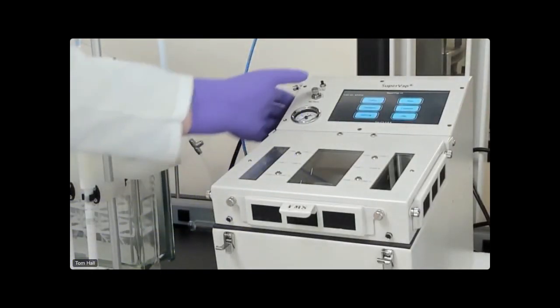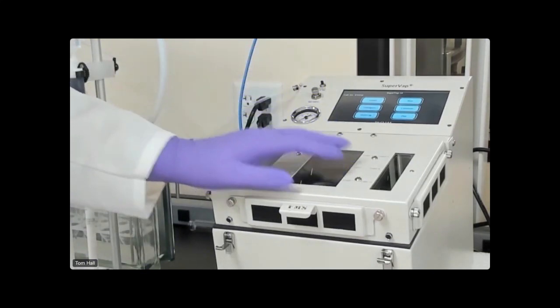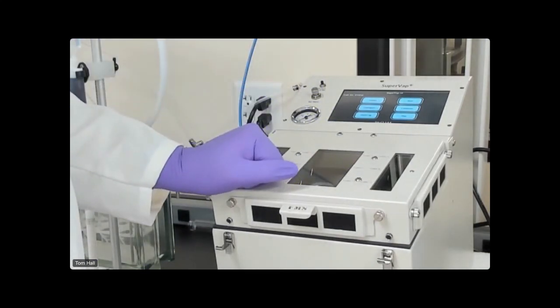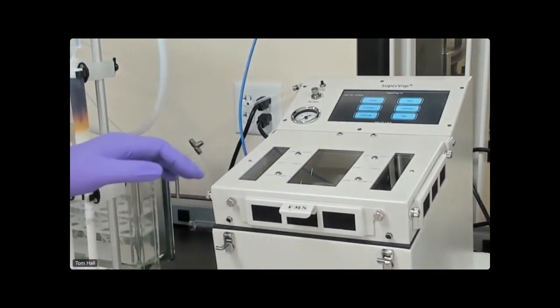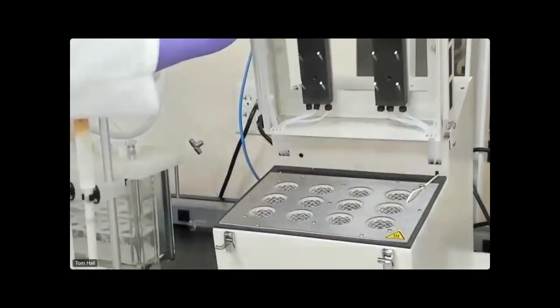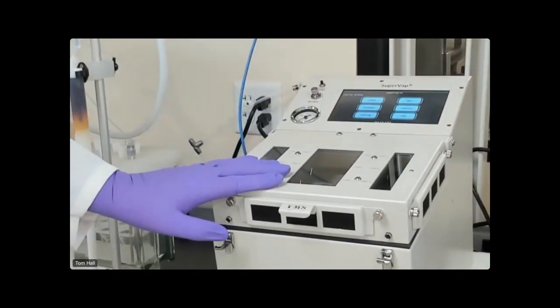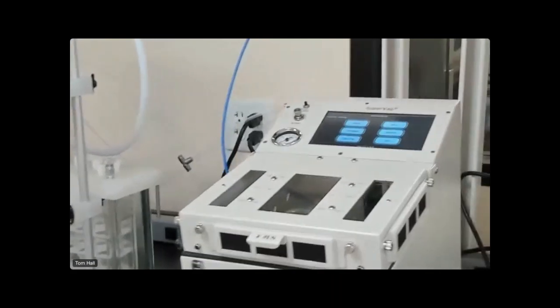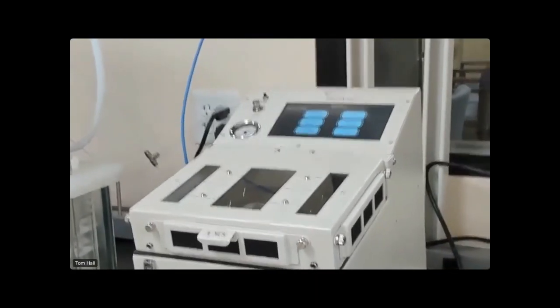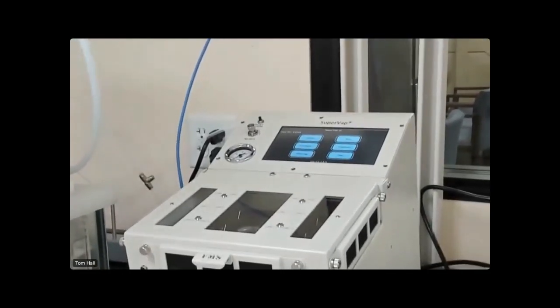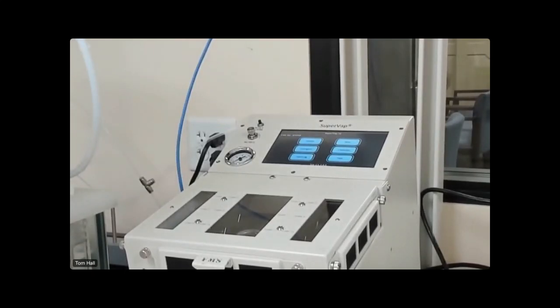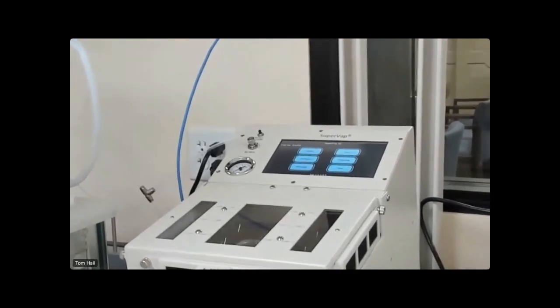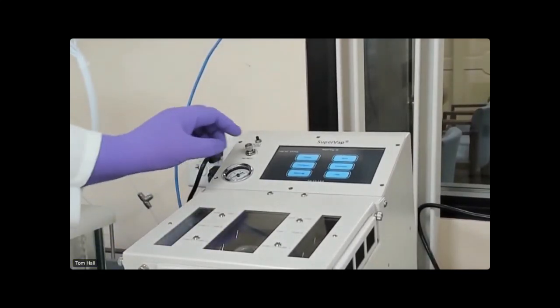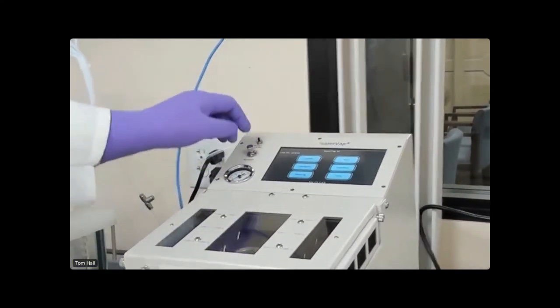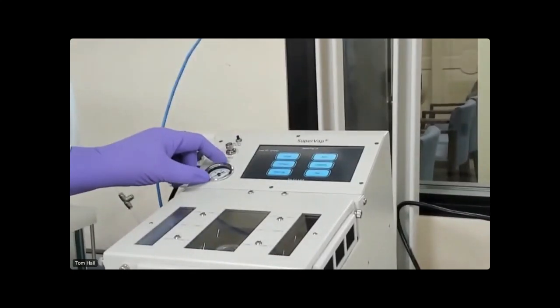Okay, here we have the alarm also, just like on the EZPrep Plus. There's an infrared beam in the bottom of each of these 12 openings, and depending on the tapering end of the tube, it either stops at half a mil or 1 mil from final volume, and the alarm bell sounds, so we can pick it up. This is the pressure gauge here. This is the regulator, and you set the amount of flow you want.